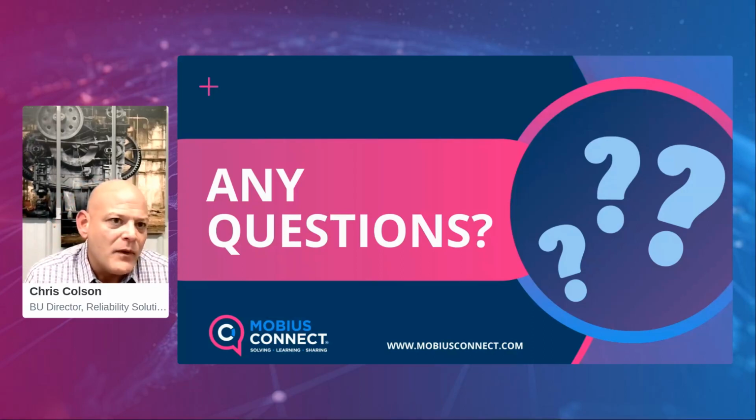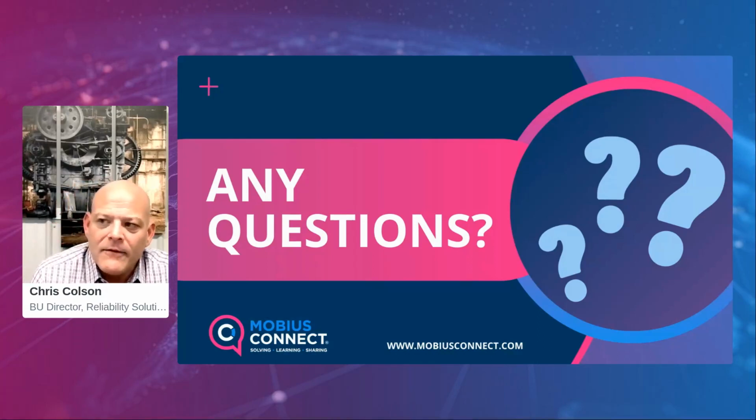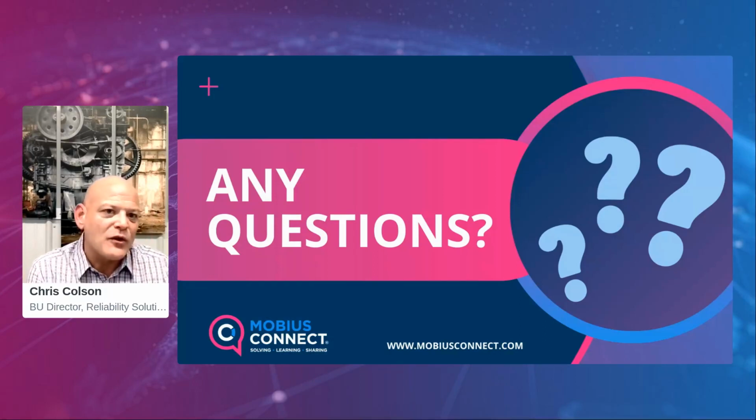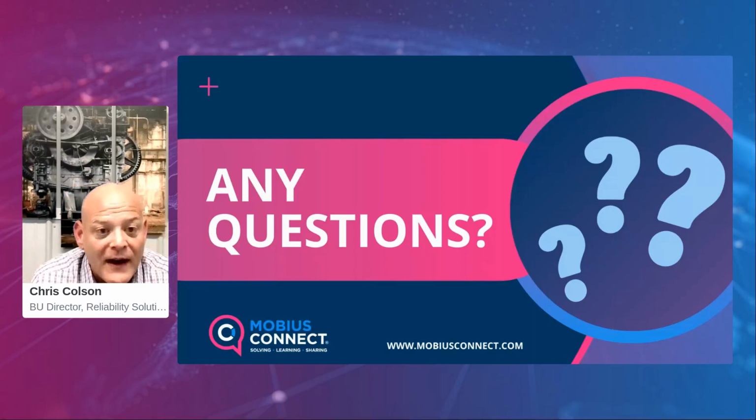We then look at criticality. If you don't have criticality, we're going to tell you you need to get it because it's extremely important. Again, to help us make better overall business decisions, we really need to have a formalized criticality. So criticality is also one of those parameters that we use to calculate. From there, we look at the frequency of failures and historical failures, and we use an element of that to weight your assets that are currently being monitored versus the assets that are not being monitored. That changes the risk, because if we're not monitoring those, we have a higher risk than the ones we are monitoring and have effectively been able to identify defects on previously. So it's a rather dynamic factor.